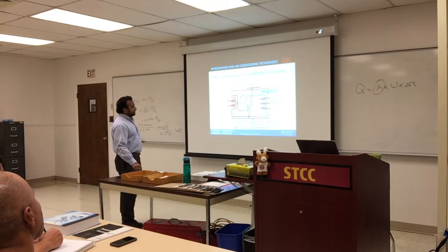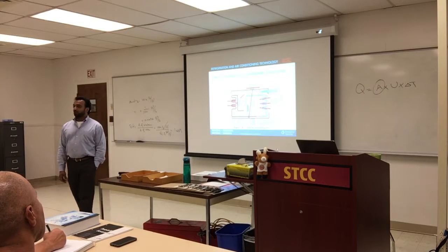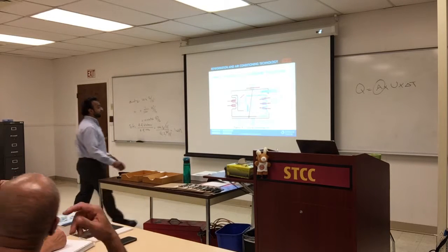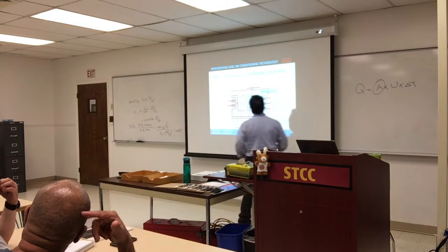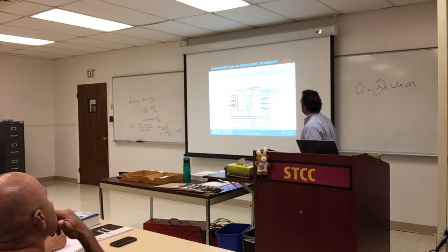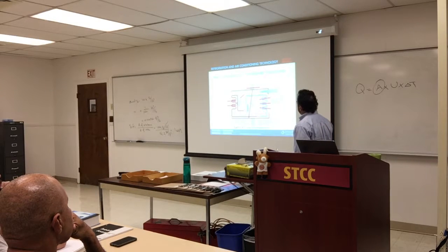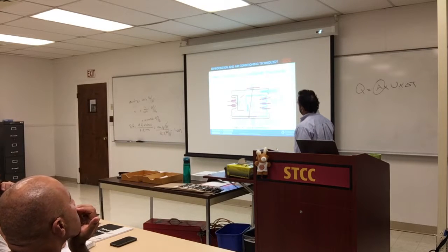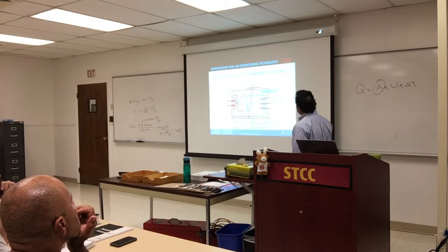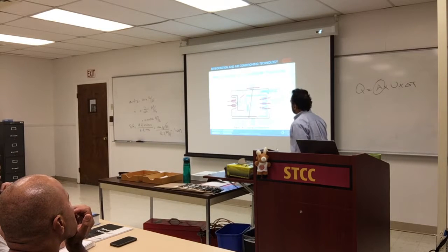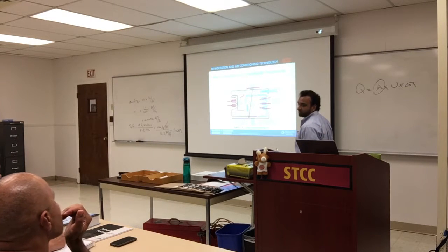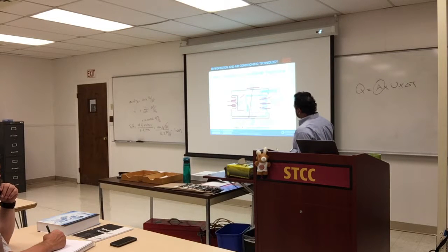Okay, we'll spend some time looking at this beautiful picture that can be a little bit intimidating, but this is the basis of heating and cooling. Let's look at it from stage one. This is the coil, has the cold refrigerant in it, which is evaporated. We have a cooling coil at 40 degrees Fahrenheit, absorbs heat from the room at 75, and you run air through it, and the air is moving through suction using the fan. This fan here is sucking the air inside from the room.